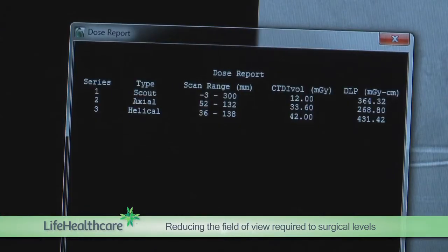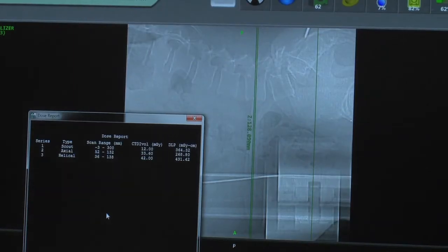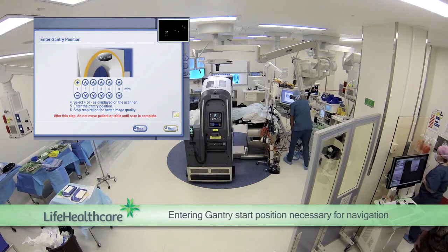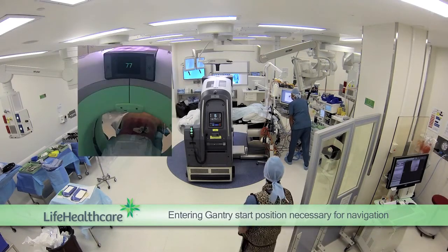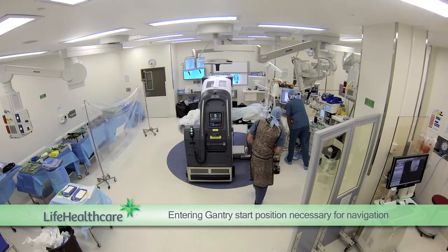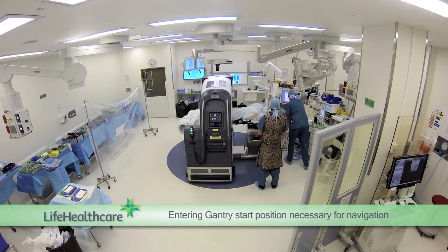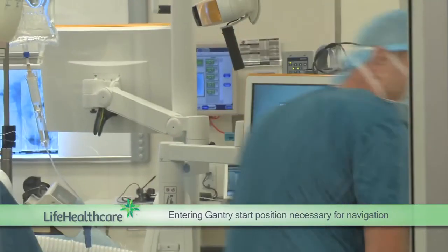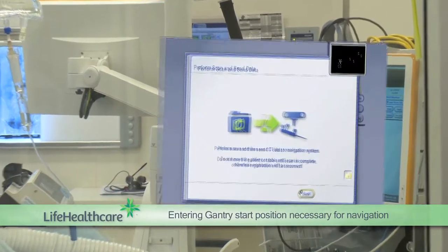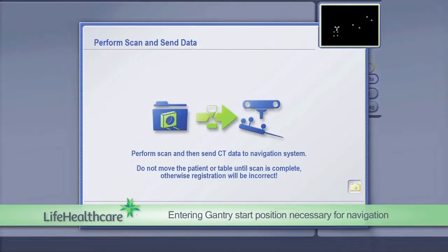Axial scans are required to comply with TGA requirements for navigation. Once the acquisition is planned, it's very important to enter the start position for the scan to the navigation system, noted on the gantry. It is paramount to get this number correct, as all of the calculations and communications between the various arrays and cameras are determined from this point.